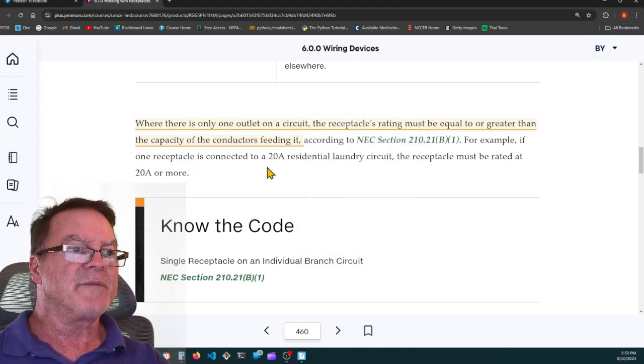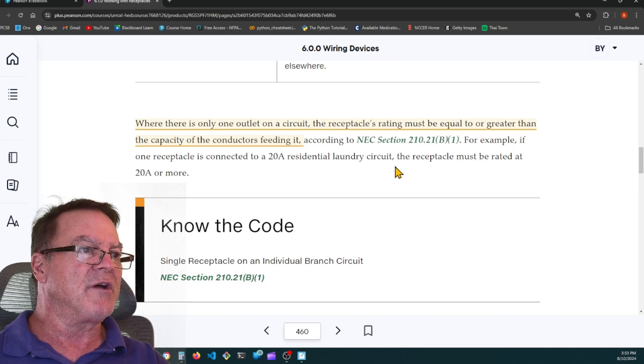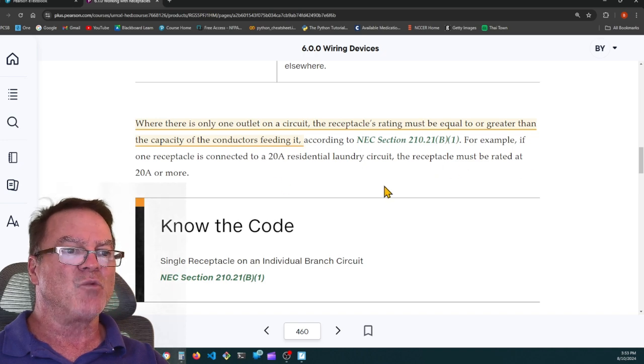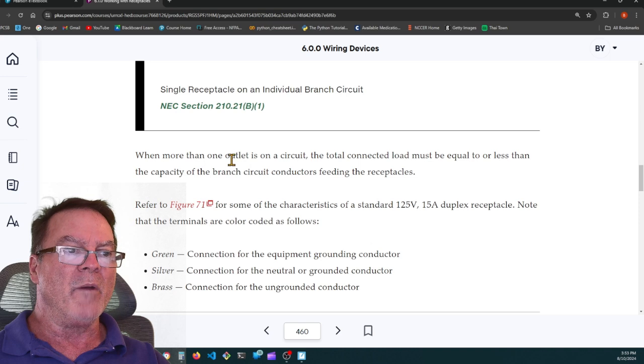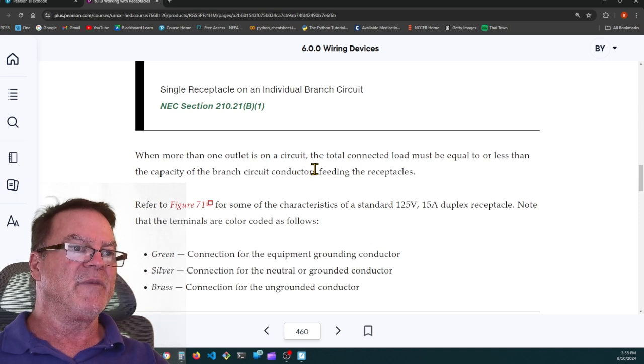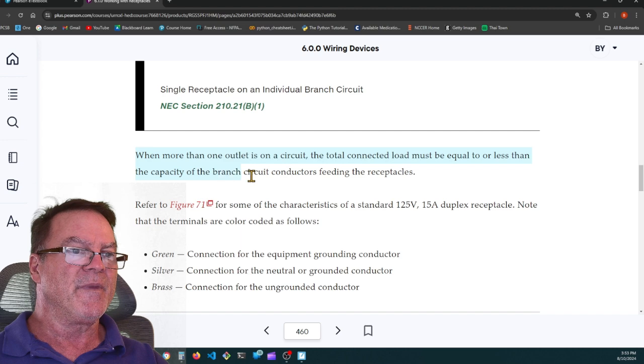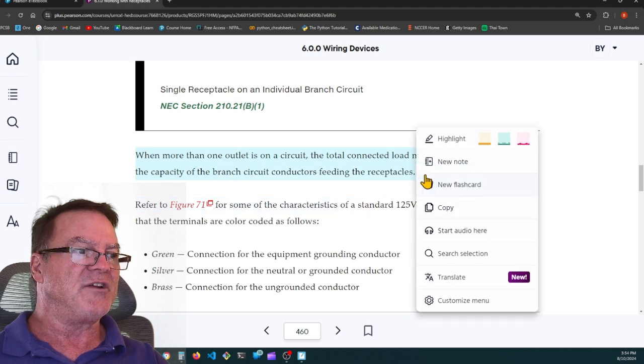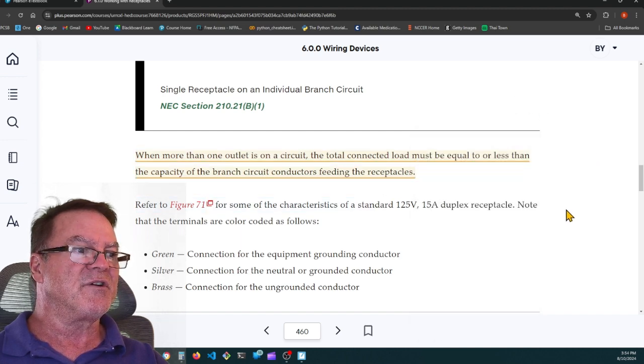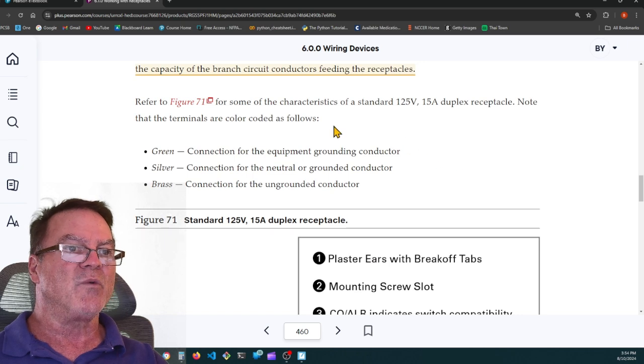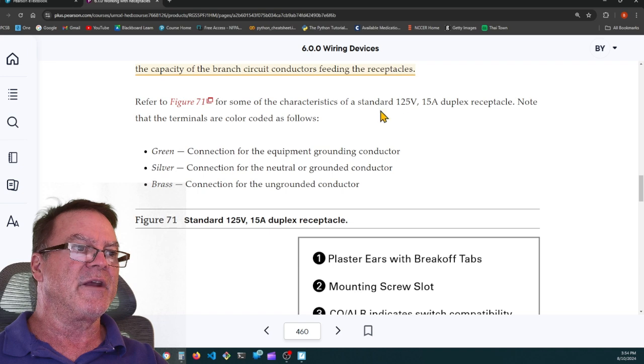For example, one receptacle is connected to a 20 amp residential laundry circuit. The receptacle must be rated at 20 amps or more. When more than one receptacle outlet is on a circuit, the total connected load must be equal to or less than the capacity of the branch circuit conductors feeding the receptacles. So when you have a 20 amp small appliance branch circuit, you're allowed to put 15 amp or 20 amp receptacles on that circuit.